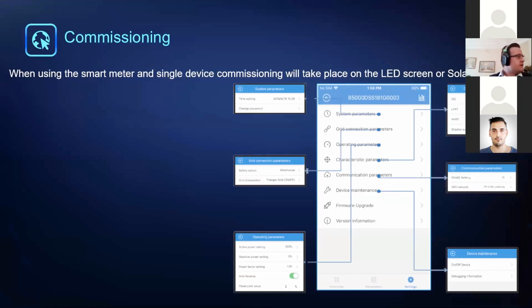For our commissioning, when using a smart meter and a single device, the commissioning will take place on the LED screen of the inverter. And should it not have an LED screen, the Solar Go app will be used. So via the inverter's direct Wi-Fi, you can connect to it, run the Solar Go application, and then we can configure the inverter from that application.